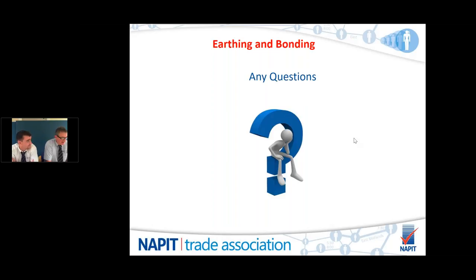Plastic pipe obviously doesn't need bonding. You will get plastic gas one day probably, but not at this present moment in time. It will either be screwed steel or it'll be copper. So gas is usually needed to be bonded, most definitely. Plastic throughout the system doesn't need bonding in any way, shape or size, because obviously it's an insulating material and can't become live. If there are sections that are metal, then the PowerPoint showed how you can determine whether it is an extraneous conductive part or not.